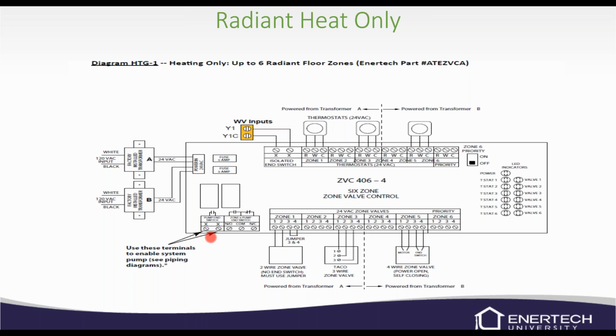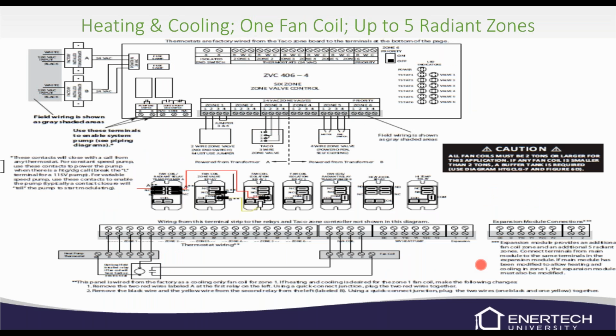So if you had a pump in between your zones and your hydraulic separator, that's where your system pump would be, right here. And then as you can see on the top, you've got your thermostat inputs, and on the bottom, obviously your zone outputs. And then it's got some LED indicators as well, to let you know which thermostats and valves are calling and open. This is the heating and cooling, 1 fan coil up to 5 radiant zones.